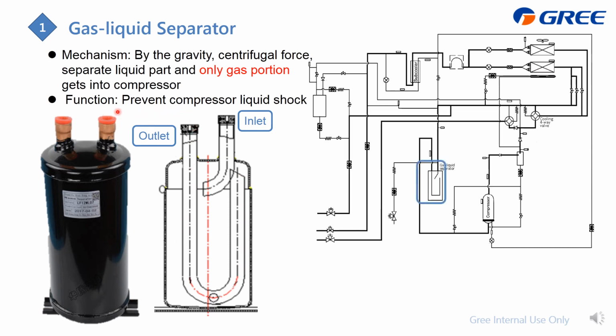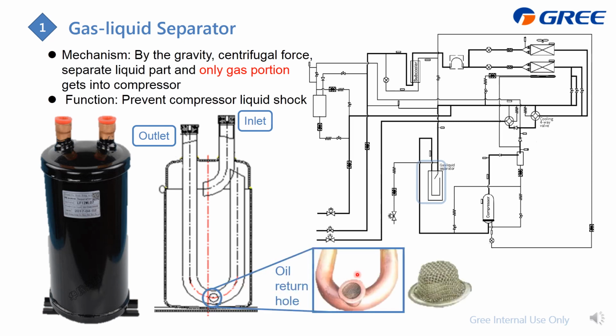And the function of it is just to prevent liquid hammer in the compressor. And also you will find a hole here, which is actually this one. There is a filter at the surface. The purpose of this one is to let the oil flow into this one to lubricate the compressor, not the liquid refrigerant.